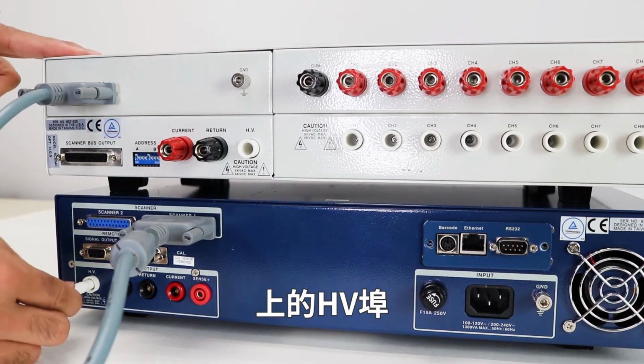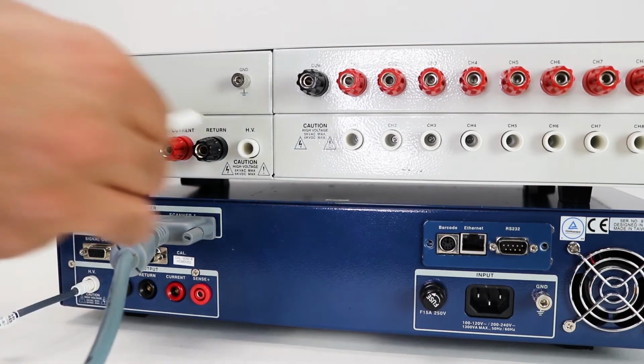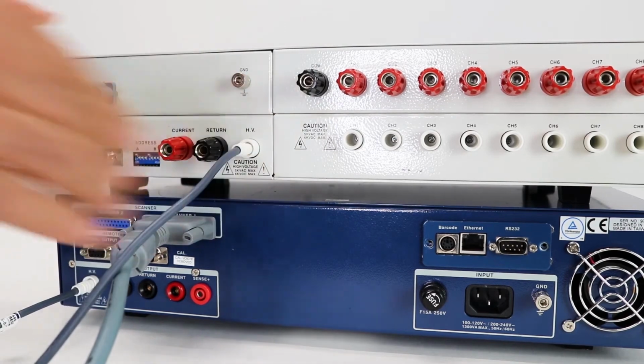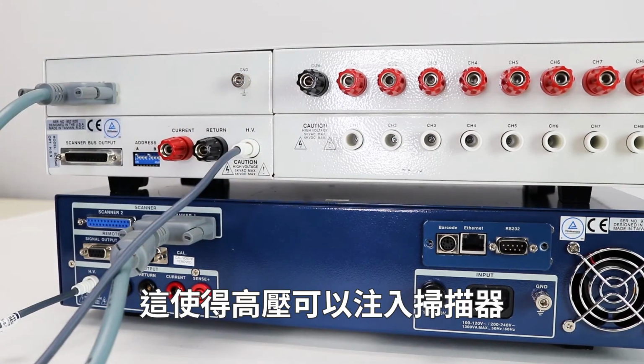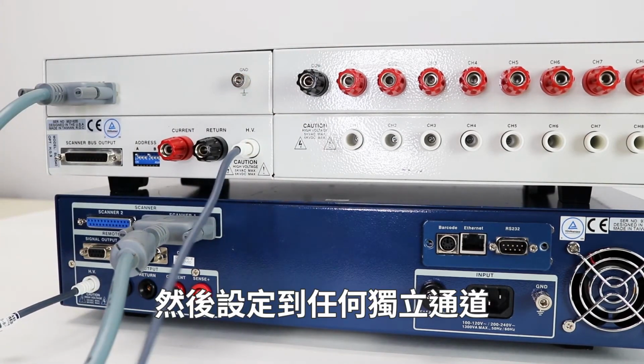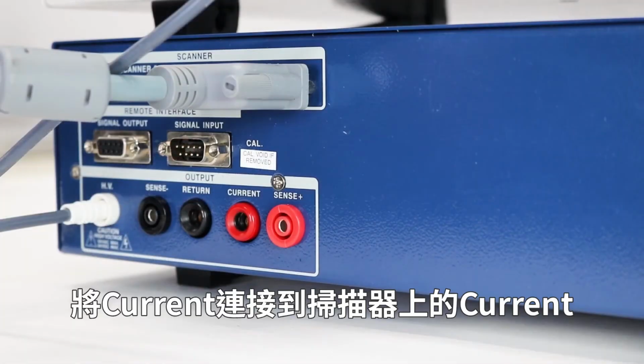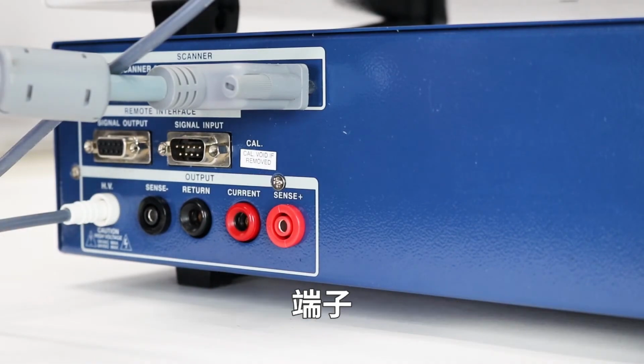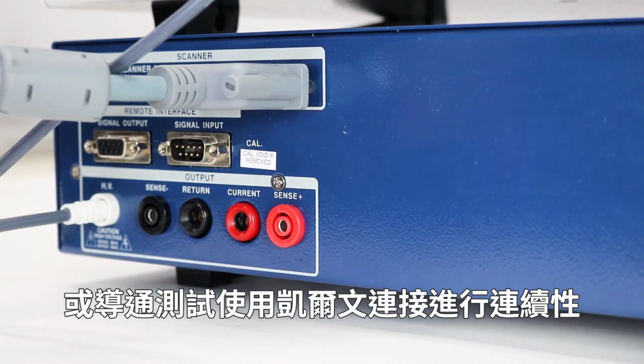Connect on the high voltage port on the HypotULTRA to the HV port on the scanner. This allows high voltage to be injected into the scanner and then set to any individual channel. Next, connect the current to the current port on the scanner if running a ground bond or continuity test.